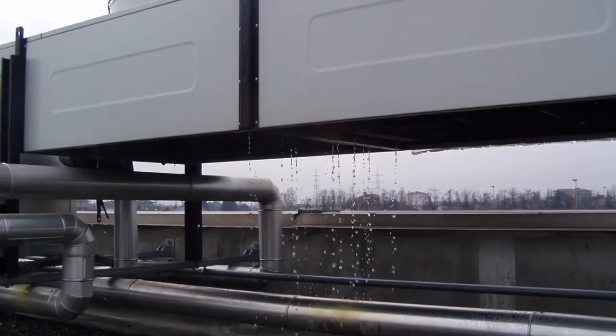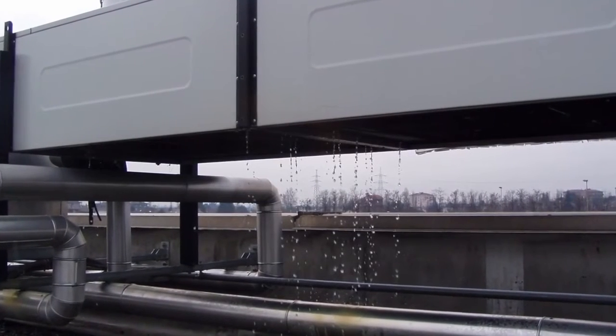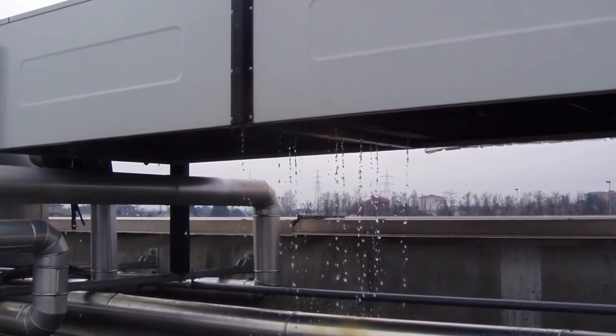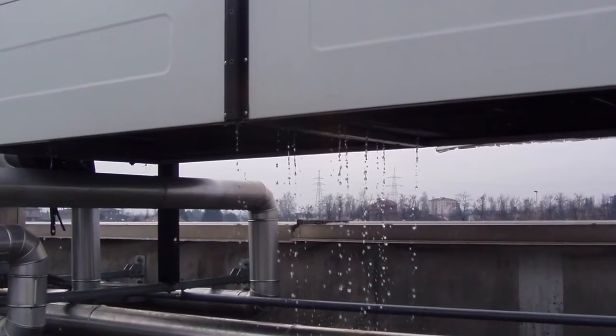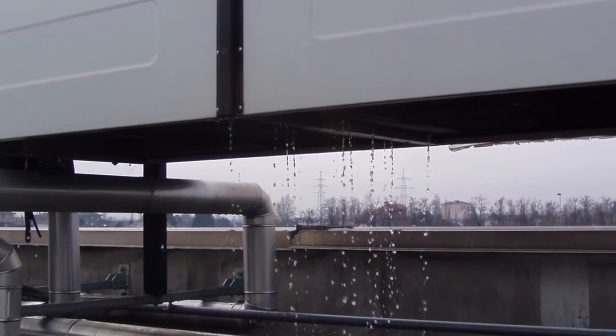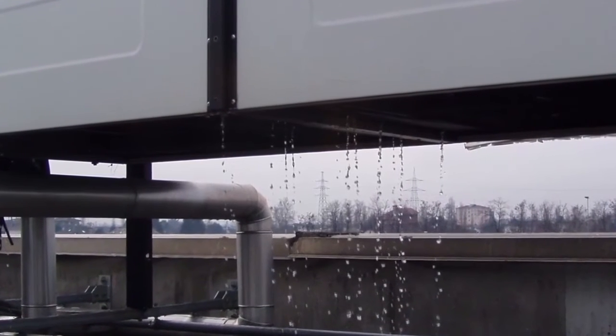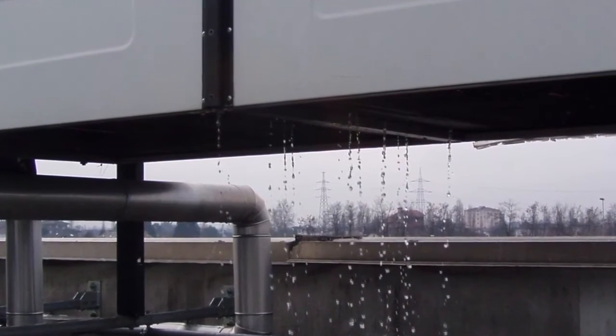I will provide an example: all vacuum pumps. When we cool the water of the liquid ring vacuum pumps, these pumps cannot function with water and glycols, but must be supplied only with water. In these cases, an exchanger like this has limitations because in winter it is obviously exposed to freezing temperatures. If we proceed to halt the plant, there is a risk that the water inside the pipes will freeze, causing permanent breakage, potentially damaging the radiator. I assure you that this kind of damage is very heavy and extremely difficult to recover or repair.